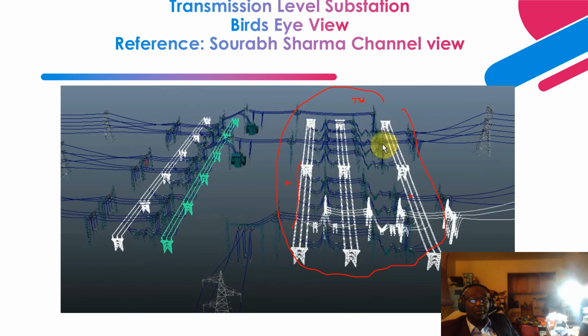In a round configuration, the civil engineers design these buses to carry continuous rated current and also to withstand the maximum short circuit current, the asymmetrical current, and the resultant electrodynamic, electromagnetic forces. If you have a fault, these tubular buses encounter that force and it shakes them.